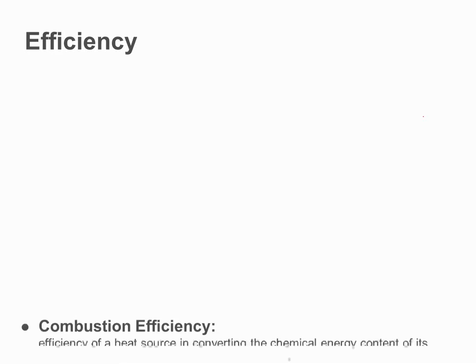Thermal efficiency is kind of the opposite. We use the temperatures of the water going in, so we measure basically what's going into the building, and we assume everything else is going up the stack. The difference between combustion efficiency and thermal efficiency is the boiler jacketing itself. How much heat is that boiler losing on the jacket? AFUE is the residential version of that.